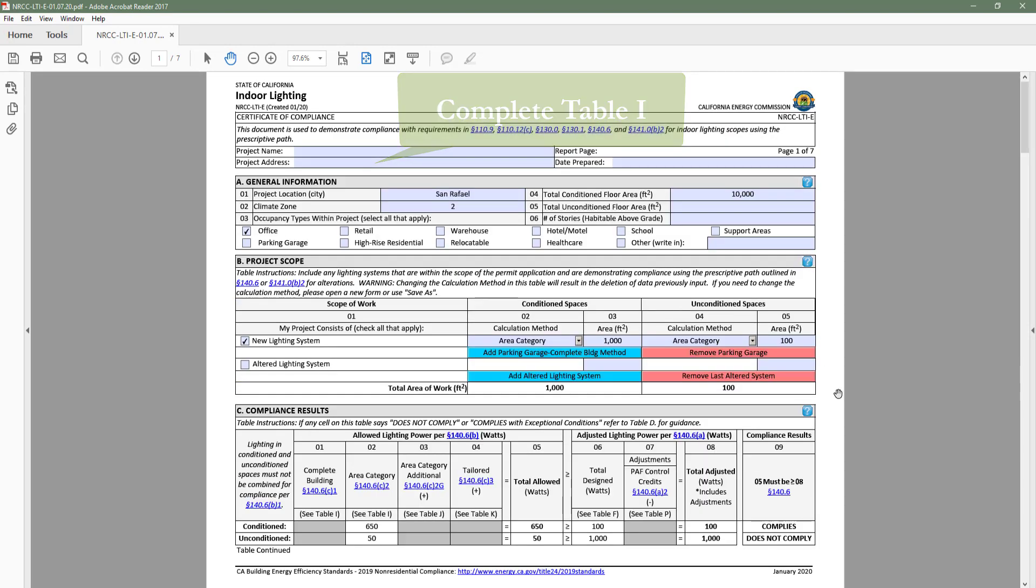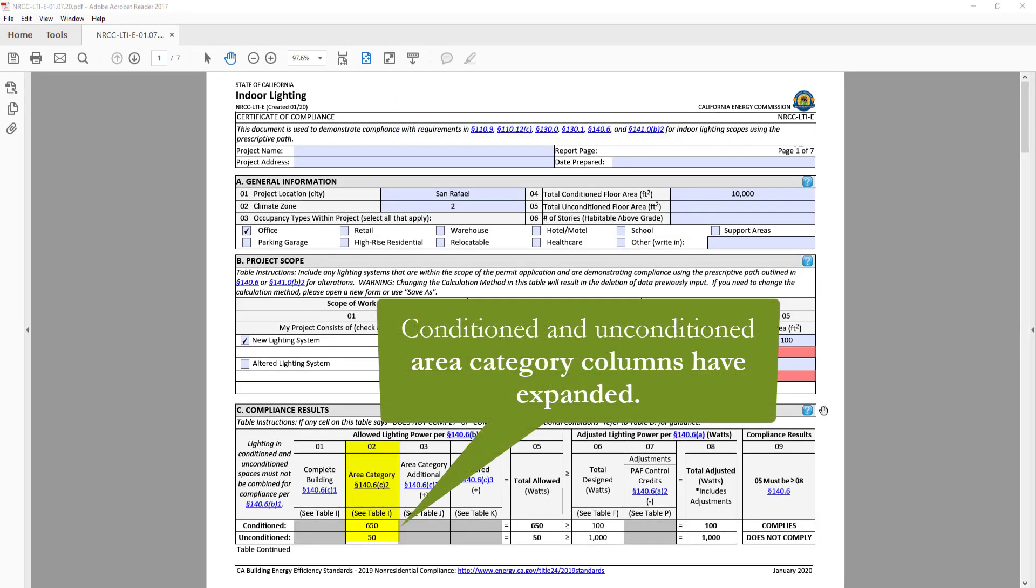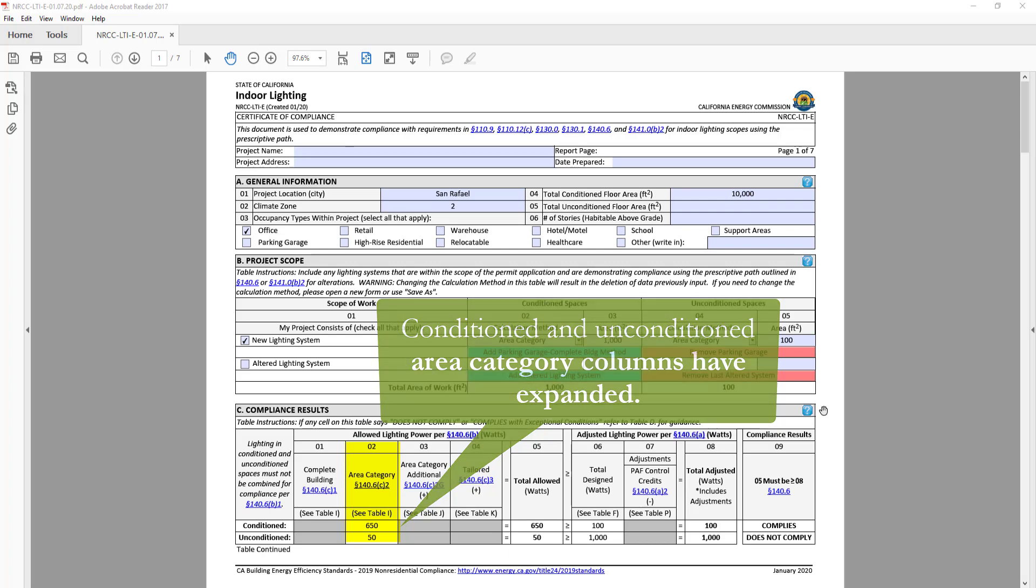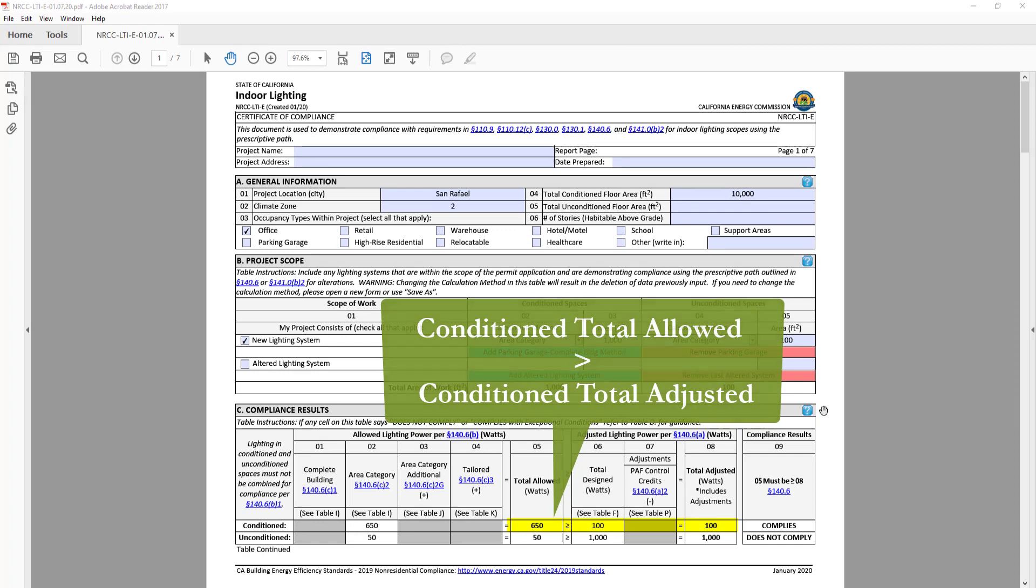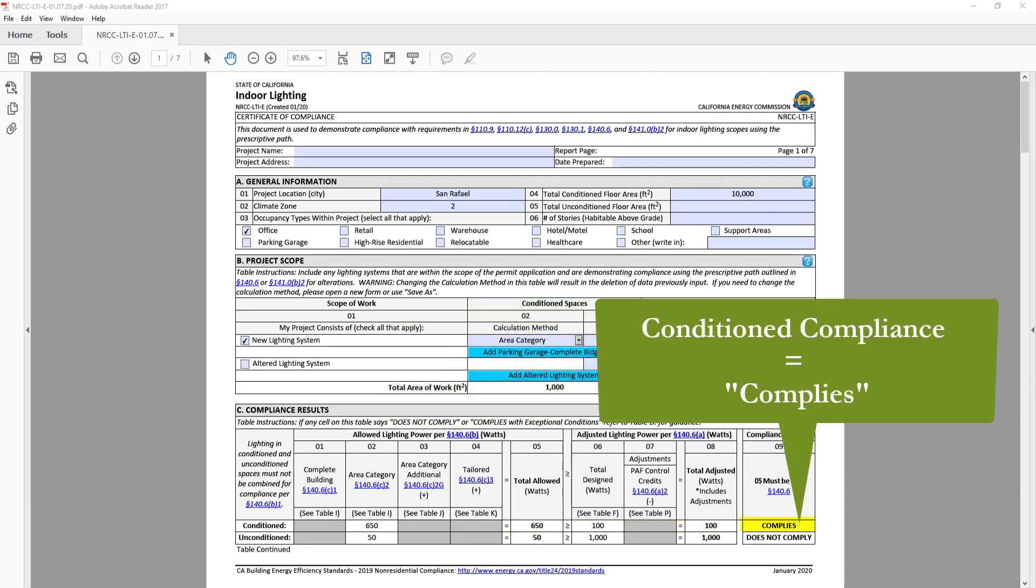When we head back to table C, you'll notice that the area category column for conditioned and unconditioned space has expanded. In the conditioned row, the total adjusted lighting power is less than the total allowed, so the compliance row indicates complies.